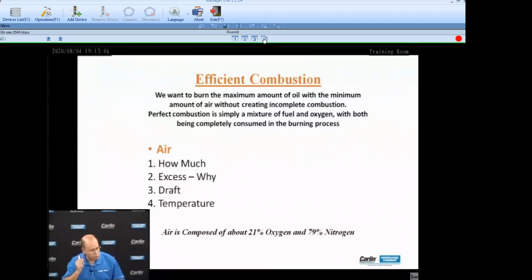Draft. Do we have draft? Is it negative draft? Is it positive draft? What are the consequences of good draft, bad draft? Those are the things that we will talk about. And temperatures. What are the different temperatures? Well, we take combustion readings at steady state, static temperatures. So we can't take a combustion test when the burner first starts. We have to allow the equipment to reach its steady state operating temperature. And what about ambient temperature? What about the temperature of the air that's coming into the combustion process? Is that of importance? Well, all these things are, and they do matter, and we'll discuss it.